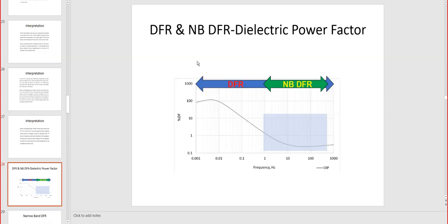This one is, we go to the next type of test, which is after we discuss the power factor and the capacitance. Now we move on to the actual dielectric frequency response. What is the dielectric frequency response? It is nothing else but the power factor reading at different frequency. So if you look at the bottom on the axis of this graph, we got frequency from 1 millihertz, so 0.001 hertz, up to 1000 hertz, which is 1 kilohertz.